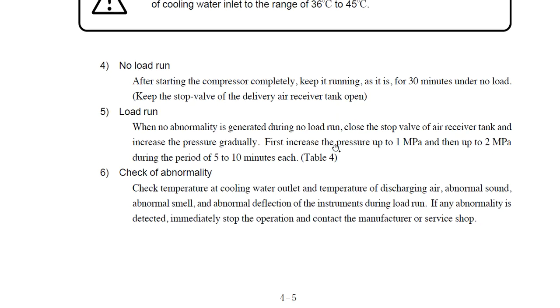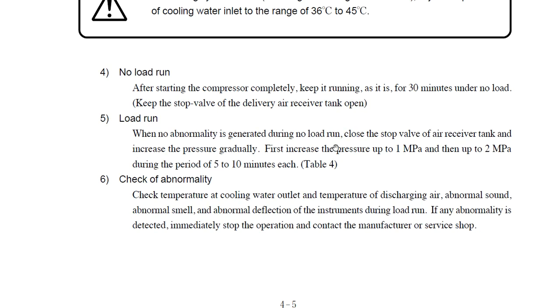After a major overhauling or some jobs that we have done on the air compressor, the best choice is to run without load. The no-load run is the starting of the compressor for 30 minutes under no load with the stop valve of the delivery air receiver tank open, so there is no increase of pressure. After we have tested our compressor with no load, we can load.